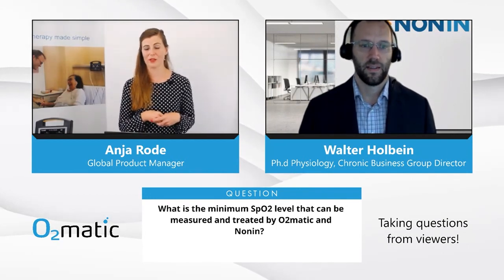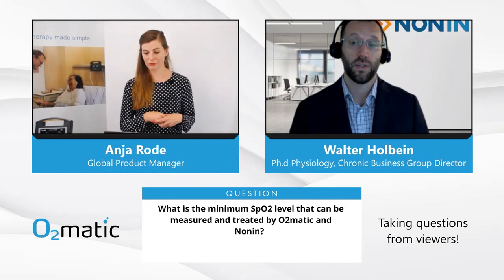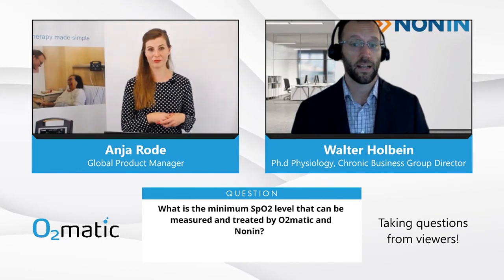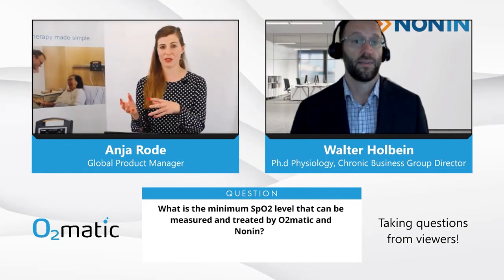So how low can you measure a stable SpO2 with your sensors, Walter? Our accuracy studies measure SpO2 and SaO2 down to an oxygen saturation of 70. We do have some data even below that, but our accuracy is measured between 70 and 100. Thank you. And we will, of course, also show the value of 70 or 66 or whatever it is on the screen of O2matic, so it's not like it's going blank. We are using your sensors and we'll follow the value that they give us.